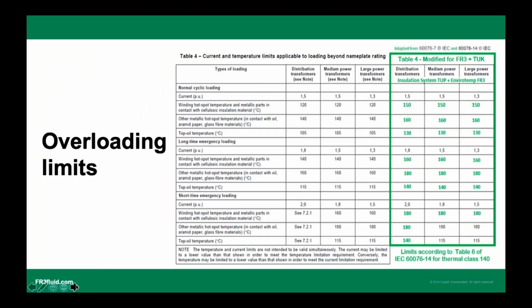Okay. Why I wanted to move on to the next slide is that people ask, when my transformer goes from 105 class to 140 class, are overloading capabilities as specified in the standard applicable? And yes, even when transformers are re-rated or have a dual rating, like 1000 kVA with a normal temperature rise and 1250 kVA with IEC temperature rise, does it have overloading capability like in the standard, 60076 part 7? When we say overloading capability, yes, the standard does allow it. I specifically put a green mark here. Yes, the transformer does have overloading capability, even though they are running at higher temperature, because of their superior thermal class. So let's move to the next slide.